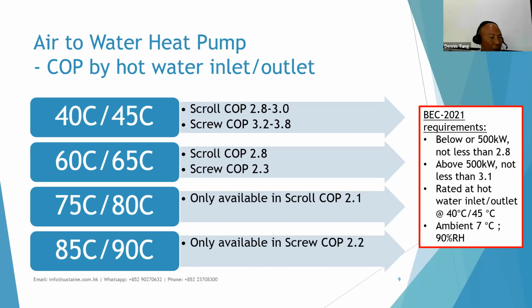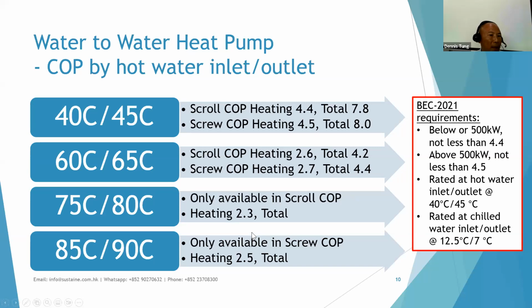Before, for heat pumps, the outlet temperature was very low, 45 degrees Celsius, and later on 65 degrees Celsius for the heat pump hot water outlet. But nowadays, 80 degree and 90 degree hot water outlet temperatures are widely available, and that can be used for the design of hot water systems for very large buildings. Where we have a large building, we have a large system, and we need a much higher temperature for the losses in the pipework and in the heat transfer unit. For the water-to-water heat pump, you can see that the COP is much higher, and it can also achieve a very high hot water outlet temperature.